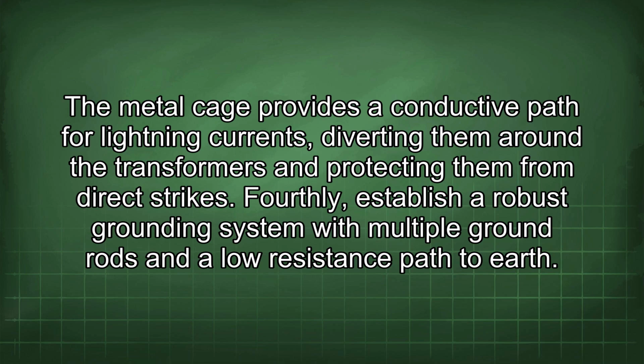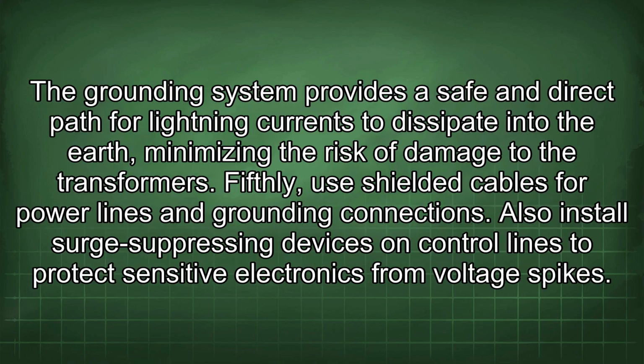strikes. Fourthly, establish a robust grounding system with multiple ground rods and a low resistance path to earth. The grounding system provides a safe and direct path for lightning currents to dissipate into the earth, minimizing the risk of damage to the transformers. Fifthly, use shielded cables for power lines and grounding connections. Also install surge-suppressing devices on control lines to protect sensitive electronics from voltage spikes.